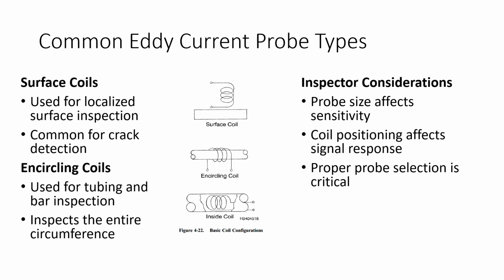And then we've got inside coils. This would be something that would be sent inside a heat exchanger. So we can check and see if the heat exchanger tubes have some kind of defect or discontinuity that we need to address. So inspector considerations: the probe size is going to affect the sensitivity of what we've got going on. Coil positioning is going to affect the signal response, right? Where are we putting that coil? Is it close to it, not close to it, wherever? And then proper probe selection is also going to be critical. So these are some things that we need to take into account.